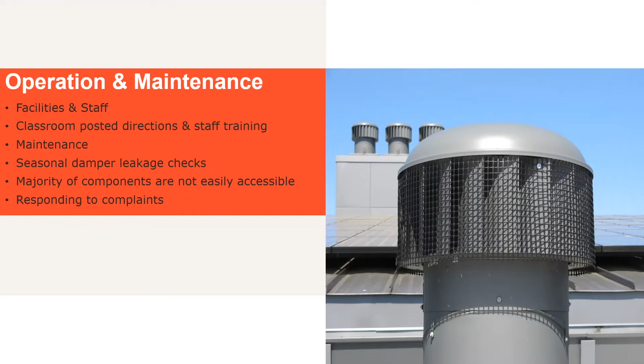Let's see, this is one of the heat recovery units, 2 of them in one of the mechanical rooms, pretty easy to get to. So that was great. We ended up doing full device checkouts for the commissioning and a condition assessment of components that weren't working, adding that metering and trend review so that we could start isolating the net and reviewing the reason why we weren't making net zero. And the controls changes, we also went through and tested slab cooling. I got to hit that button and swap it over. It took about 2.5 days to go from heating to cooling.